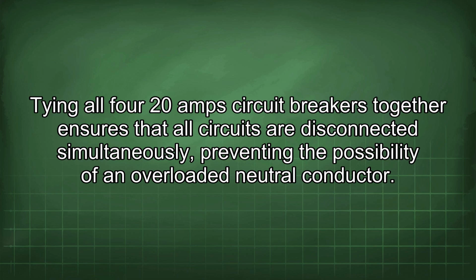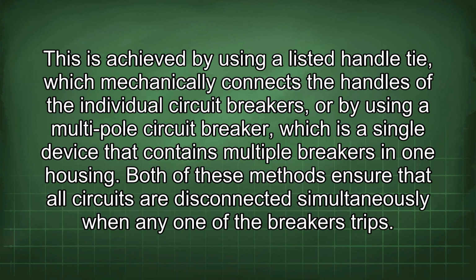neutral conductor. This is achieved by using a listed handle tie, which mechanically connects the handles of the individual circuit breakers, or by using a multi-pole circuit breaker, which is a single device that contains multiple breakers in one housing. Both of these methods ensure that all circuits are disconnected simultaneously when any one of the breakers trips.